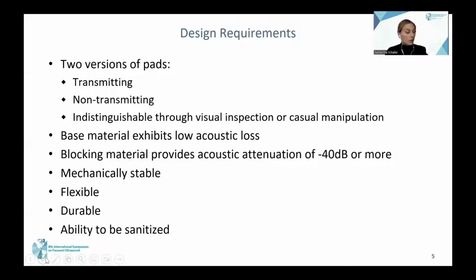So we do have a few design requirements for these pads, the first of which is that there are two different types. The first is transmitting, which means it allows ultrasound to pass through, and the second is non-transmitting, so it effectively blocks the ultrasound. These two types, regardless of which one they are, should be indistinguishable from one another through visual inspection and casual manipulation. That way, the operator doesn't know which pad is which throughout the course of the study.